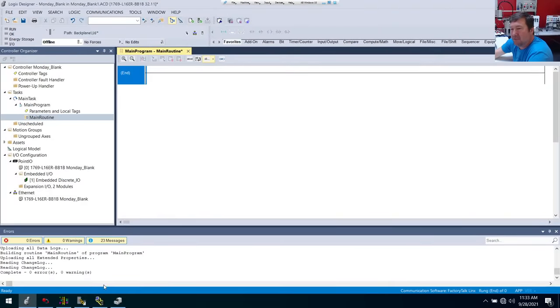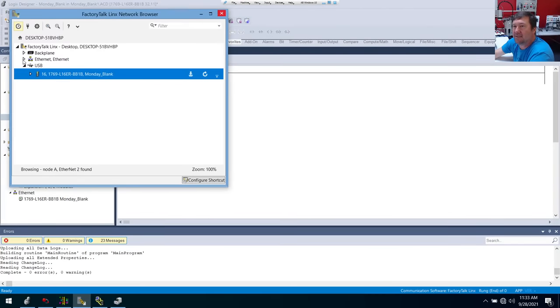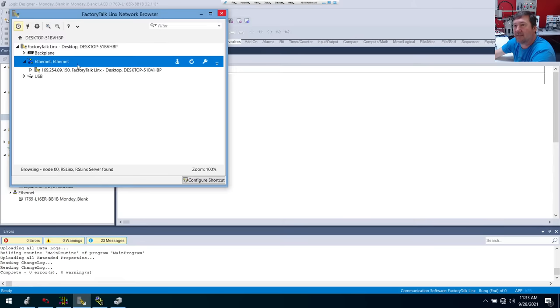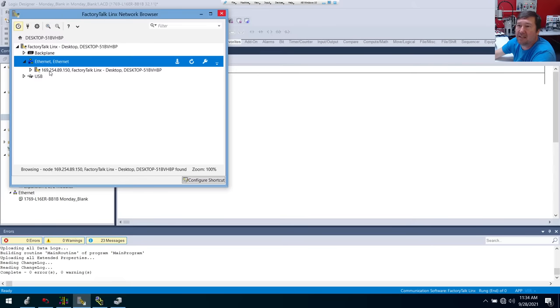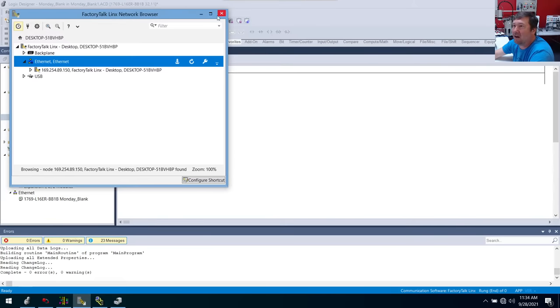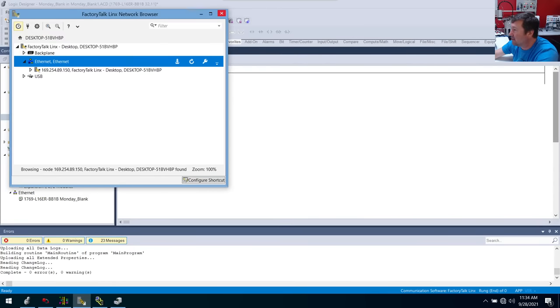What we would love to do now is go to FactoryTalk Linx and click on Ethernet. We'd love to click right here and get our PLC to show up, but that's not going to work because we don't have our Ethernet on our PC configured to communicate with these machines. One big hint you'll get is if you see this 169.254 number — if you see anything that looks like that, that means that DHCP is enabled on your PC. It's waiting on a server, and that's more of something you would have in an office environment.